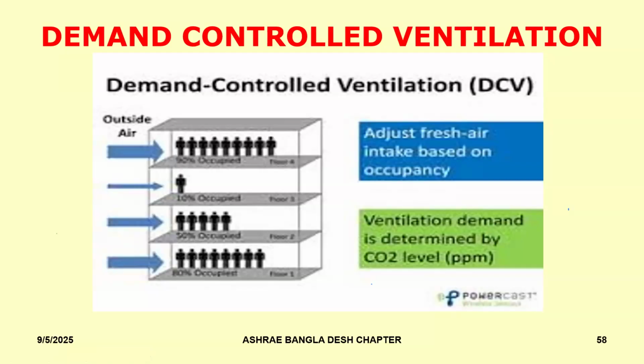How do we evaluate the demand? Well, in the case of outdoor air systems, as we said, we can calculate it based on, what is the variable here? The space doesn't change in terms of square foot. So therefore, the CFM per square foot, that part remains fixed. But what varies is the number of people. So if the number of people are less, we will supply less air, as is illustrated over here. So demand control ventilation allows us to provide as much outdoor air as is required.